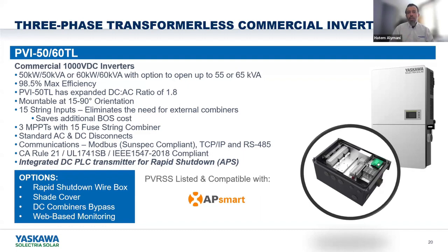It's worth mentioning here that all of our PVI products are basically two components. The upper component, as you see right here, is the power head. That's where all the logic and all the switching from DC to AC happens. And at the bottom, there is the wiring box. So when you purchase our inverter, just make sure that those two components are delivered to the field, because without the wiring box, you're not going to be able to land your strings, and you're not going to be able to meet the Rapid Shutdown requirement.